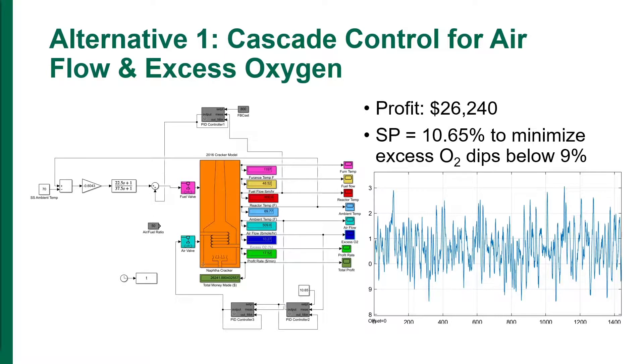While the profit was higher, the oxygen dipped below the 9% allowed value multiple times during the day. The set point had to be raised to 10.65%, but even then, the issue remained and the oxygen still dipped below 9% six times during the day.